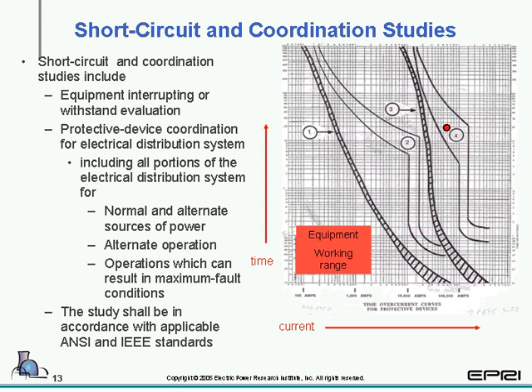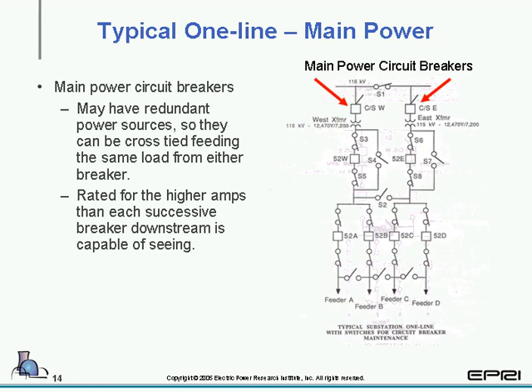So in saying that, on the next slide I'd like to take a look at number 4, or the main power. Now, typically the main power circuit breakers may have redundant power sources, so they can be cross-tied or feed the same load from either breaker. And they're rated for a higher amperage than each successive breaker downstream is capable of seeing. In this case, you're going to see we have two arrows pointed to the main circuit breakers feeding the line. Switch 1 is closed. We can open that switch and close the S2 switch. And then we can feed the feeder breakers down below from one or the other main power breakers.